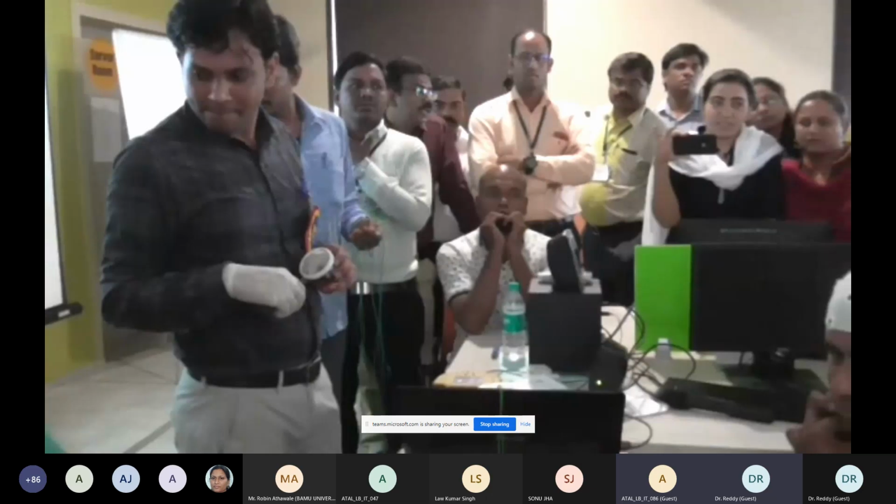Can you identify that? I'm holding that electrode gel. Can you see me? Yes, sir. I'm holding a small box where there is electrode gel, some small shampoo-type gel, which you have to apply to the channel position. Then you have to insert the electrode. Only then will that red color go to green.